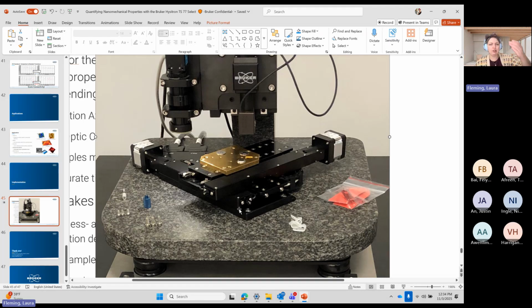You should have your transducer sitting on your desk, and the number one rule is don't hold it. People are tempted to hold onto the transducer so it can't move away from them while they install the probe. That's actually the exact opposite of what we should be doing. If you recall, the probe is screwing directly into that center plate. If we hold onto the transducer, it's much too easy to exert excess force along the indentation direction. So instead, we recommend taking a mouse pad or some sort of sticky thing, placing the transducer on it.